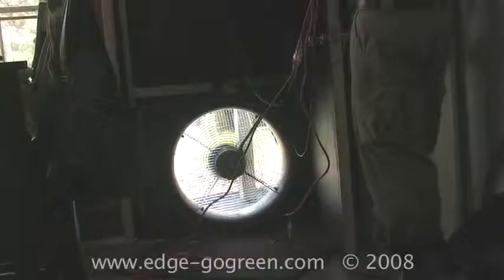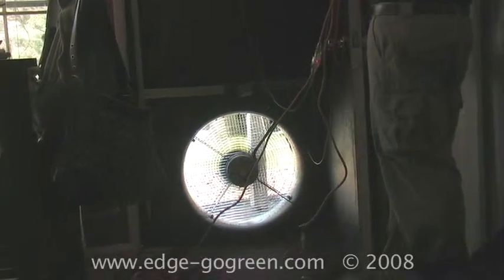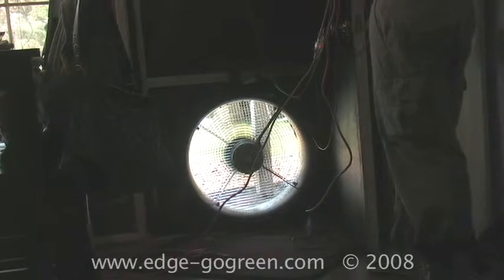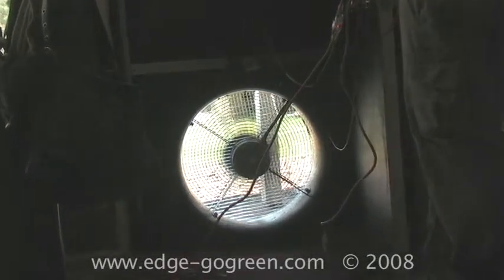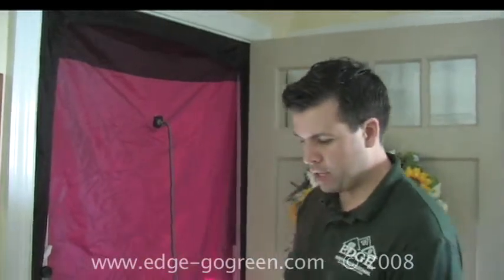For the house to compensate that pressure imbalance, it needs to bring in that much air from somewhere else in the building shell. What we're going to get out of that information is the cumulative amount of building shell leakage at natural pressures, when the house is under normal conditions and we're not elevating the pressure difference with the blower fan. So why don't we get started here and we'll do some data real quick.